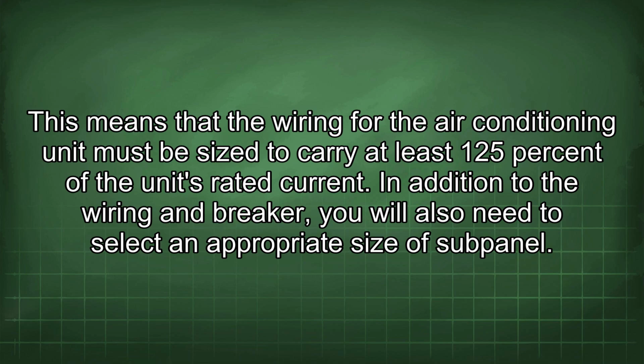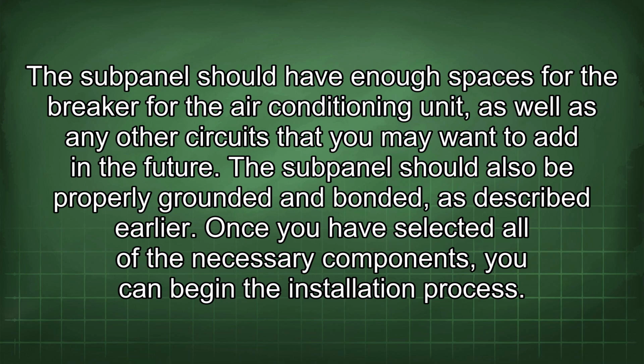unit's rated current. In addition to the wiring and breaker, you will also need to select an appropriate size of subpanel. The subpanel should have enough spaces for the breaker for the air conditioning unit, as well as any other circuits that you may want to add in the future. The subpanel should also be properly grounded and bonded, as described earlier.